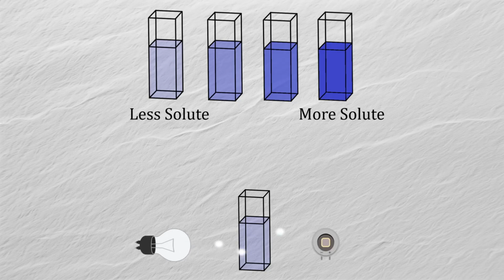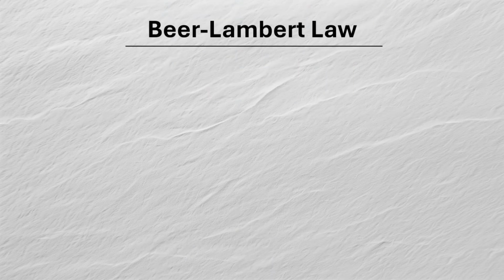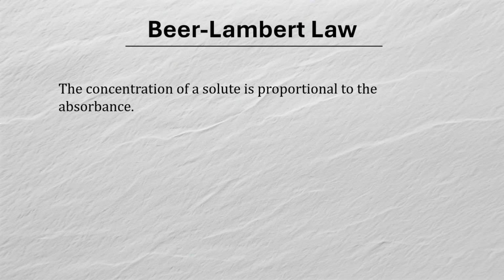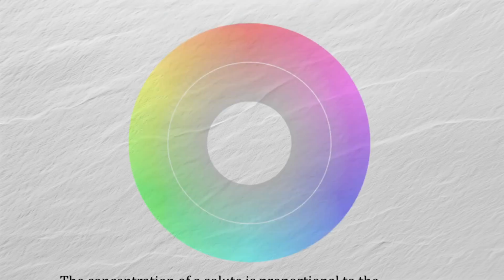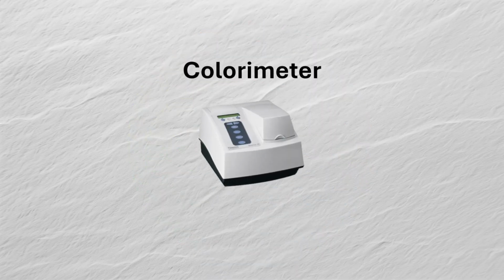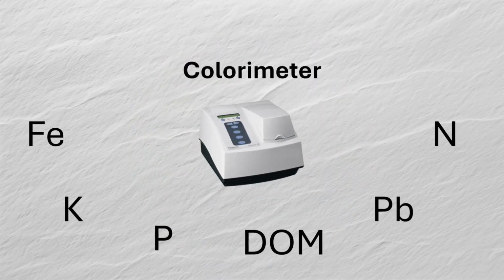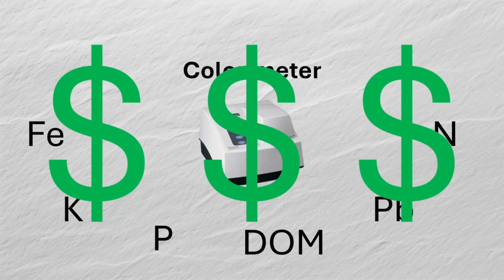This principle is an application of the Beer-Lambert law, which states that the concentration of a solute is proportional to the absorbance. Now, the color of the transmitted light is very important. You want to transmit at a wavelength that is complementary to the color of the solution dye. So this can generally be determined by seeing what color is opposite on the color wheel. Colorimeters allow the measurement of a wide range of water solutes, making them a great tool for water quality assessment. The only problem, as I mentioned, is that they are very expensive.